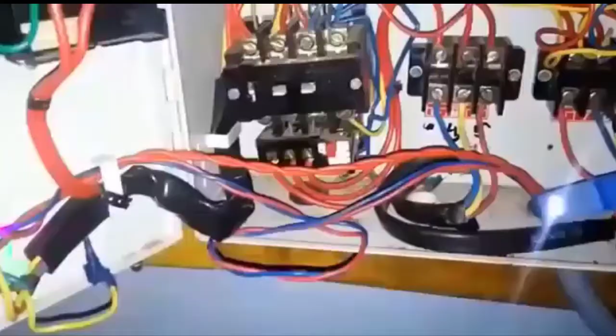Here I have installed the SCT013 100 amps split core current transformer, connected across a live phase wire, which is the R phase. This is the R phase, this is the B phase, and this is the Y phase. One phase wire is connected across the split core current transformer, which is clamp type, and its output cable runs through my main controller board. This is my main controller.